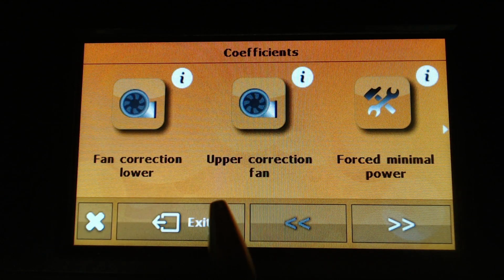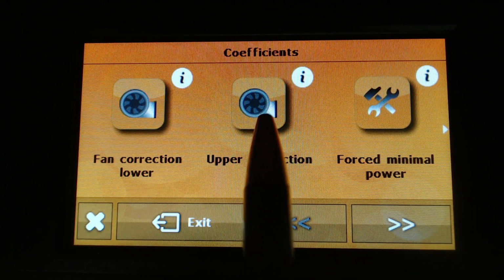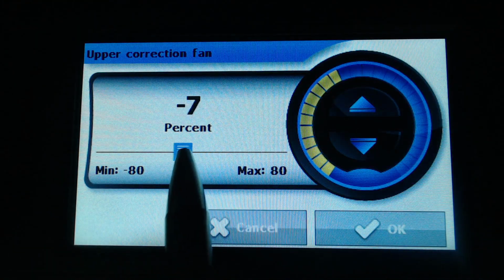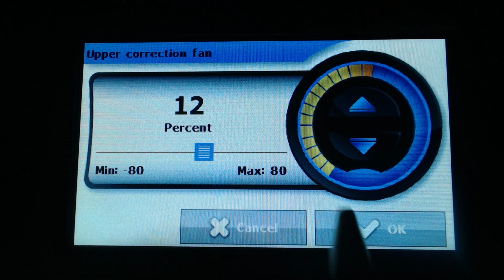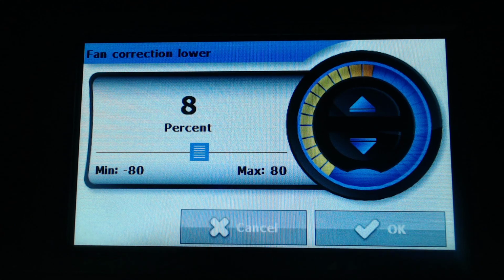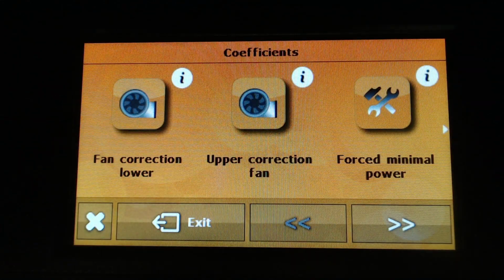Okay, again, if the flame is too big and smokes, then you need to probably increase the speed of the fan for maximal, and probably also for minimal power a little bit. Then check the flame, open the door a little bit to see the flame, check if it's all right. If it smokes, you can increase the speed of the fan a little bit more again. If it doesn't smoke, if the flame is orange in color, then you know that the combustion process is all right.